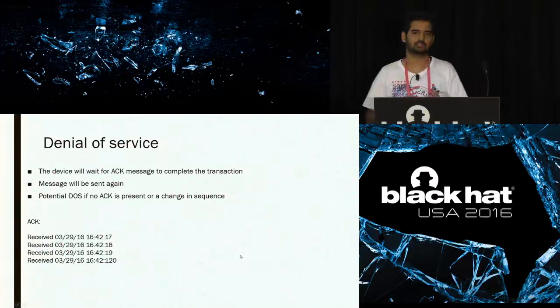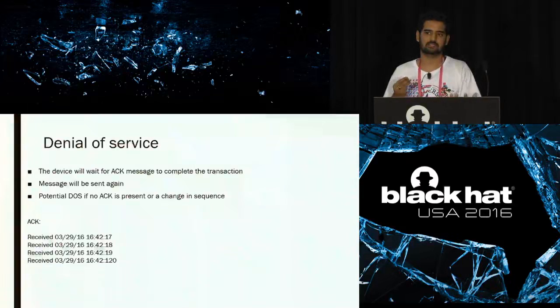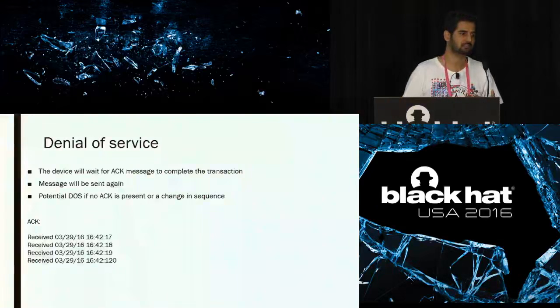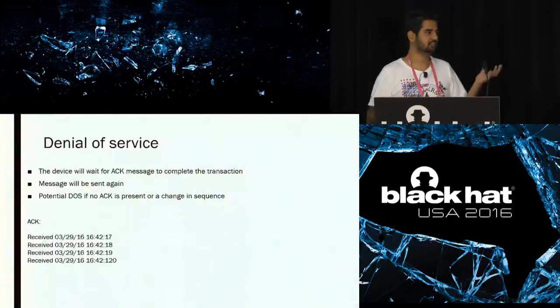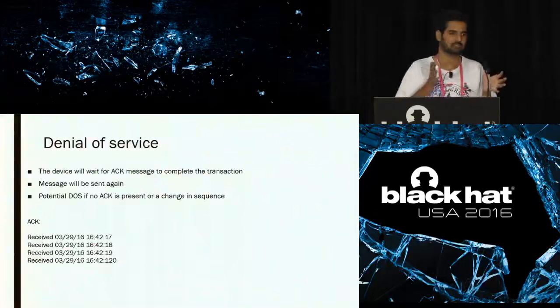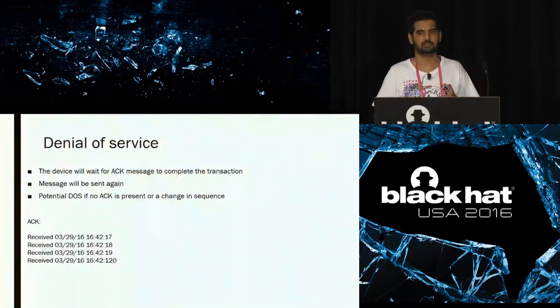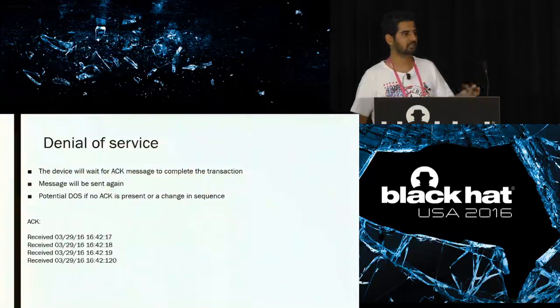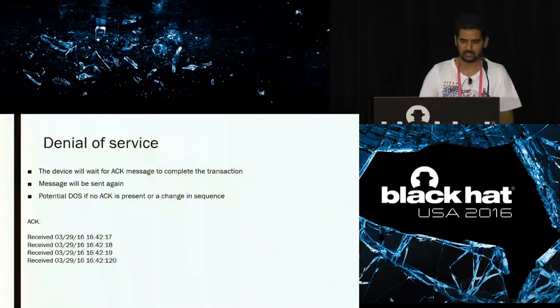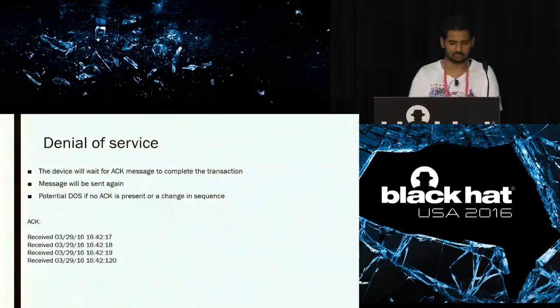What happens is the patient monitor thinks that the message is not complete, so it will send the message again and again and again. So you end up sending the same message over and over. If you have a blood pressure which is falling, like 60 or something, it'll send the same message again and again. Now that has to be configured on your device. It has to purge messages after a particular time, which is a configuration flaw that I find missing in some hospital environments. So this is a potential loss, and we'll see how it looks.